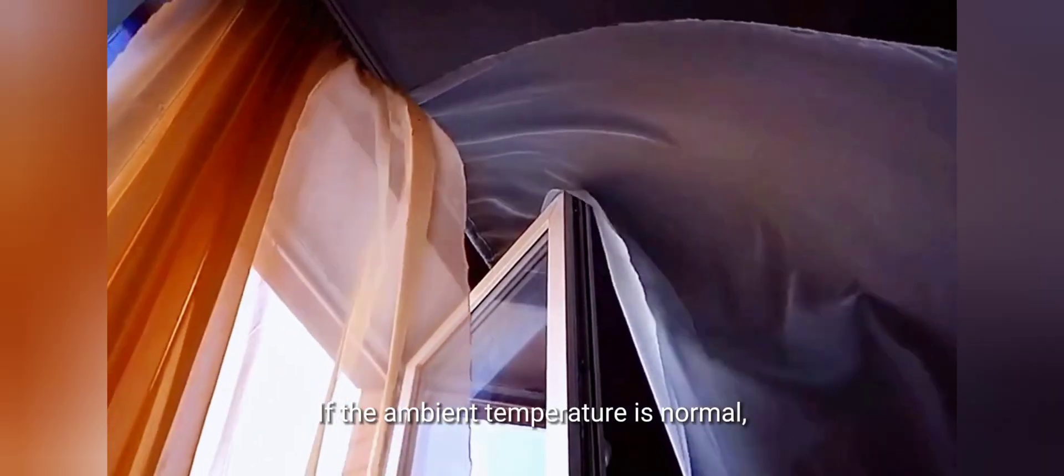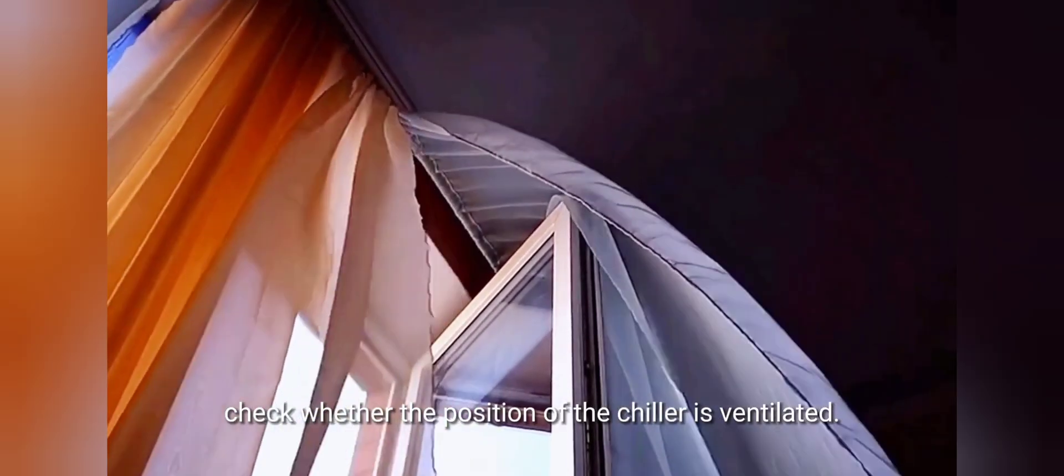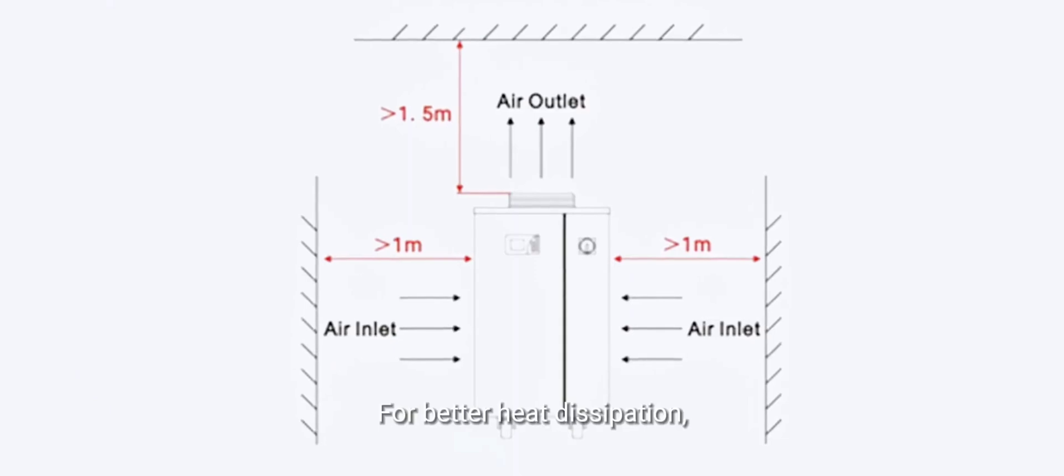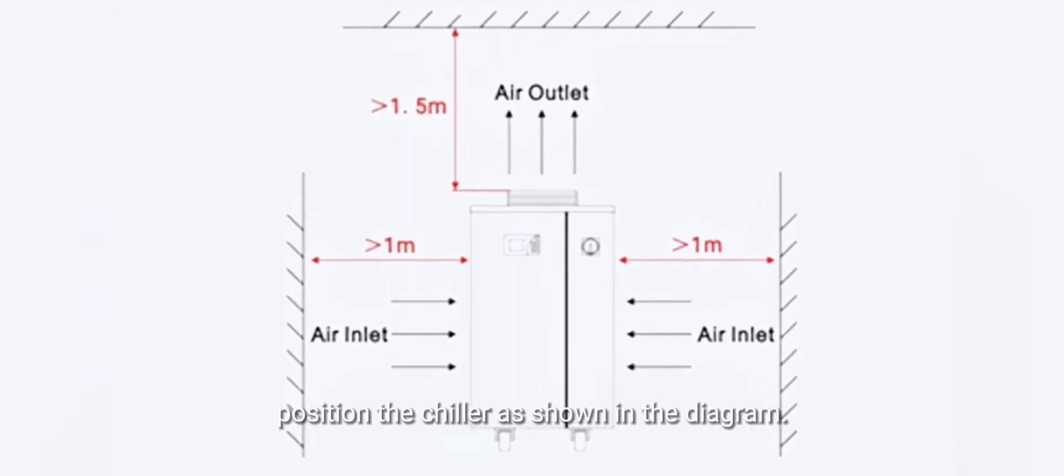If the ambient temperature is normal, check whether the position of the chiller is ventilated. For better heat dissipation, position the chiller as shown in the diagram.